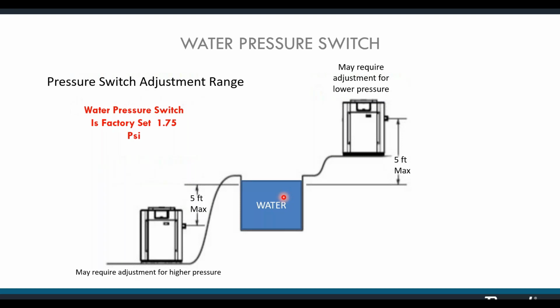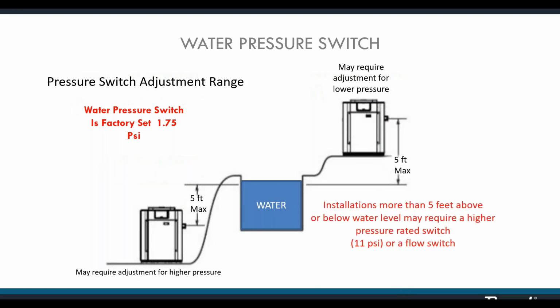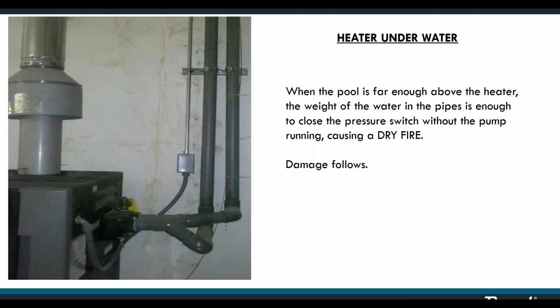And in fact, it could be pulled downward at a rate that offsets the pressure, so that there could be zero pressure up here at the heater, or negative pressure for that matter. At that point, a pressure switch isn't going to do you any good. You would need to put a flow switch on here to alleviate that problem. Here's an example of where a flow switch might come in handy. The weight of the water in the pipes could easily create enough pressure to close the pressure switch. If the pump fails, the heater won't know that, because it still has good pressure. So the heater can dry fire, and you will damage that heater.